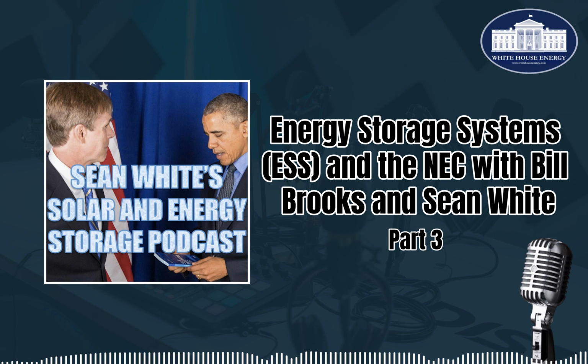Microgrid system definition, to me, is a little bit weird. Premises wiring system that has generation, energy storage, and loads, or a combination that includes the ability to disconnect from, and parallel with, the primary power source. You might think that it doesn't really work if you're off grid, because we have to have this ability to disconnect from and parallel with the primary power source. But maybe you could just have that ability, but not ever have a primary power source. Right, that's why it's written that way. And it's been adjusted in the last couple of code cycles.